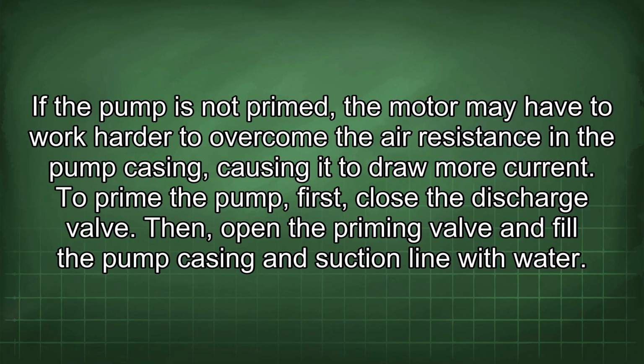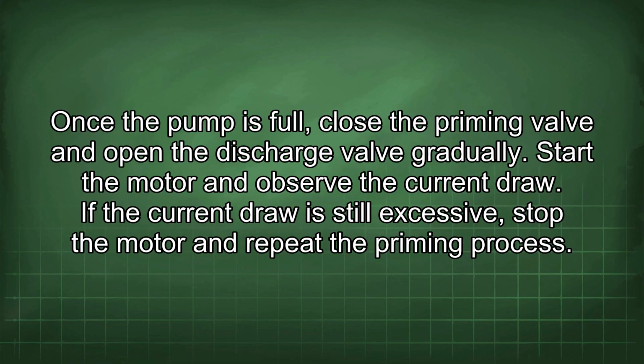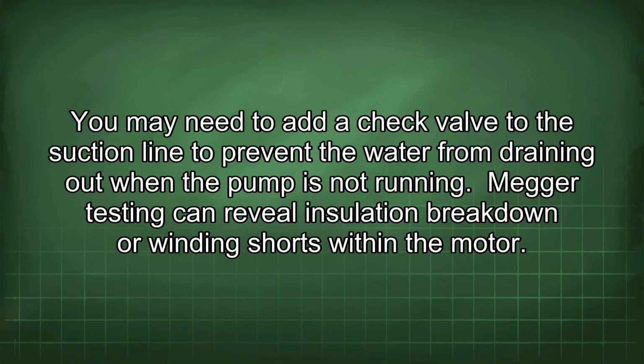To prime the pump, first close the discharge valve. Then open the priming valve and fill the pump casing and suction line with water. Once the pump is full, close the priming valve and open the discharge valve gradually. Start the motor and observe the current draw. If the current draw is still excessive, stop the motor and repeat the priming process. You may need to add a check valve to the suction line to prevent the water from draining out when the pump is not running.